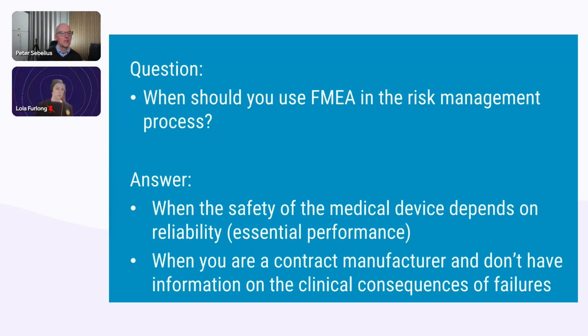There are some here. I'm going to save some of them, but let me see here. One of the questions here is from Tanas: when can we get some examples of when it's better to use FMEA or risk assessment based on ISO 14971? Well, there is actually a quite simple answer to that question. You have to use ISO 14971 risk management. FMEA is optional. At least if you use the meaning and definition as I provided here from ISO 14971 and the FMEA standard, you have to do ISO 14971 risk management. It's optional with FMEA. So it's an add-on. It's a tool that you can use. And I think that answers the question.